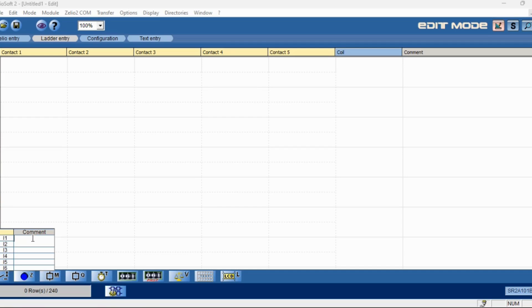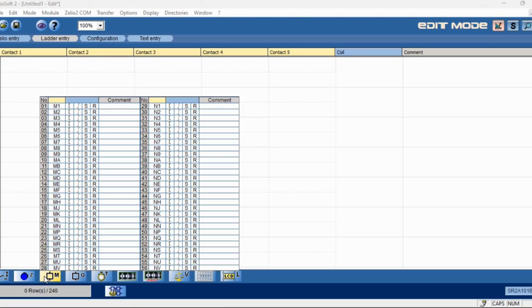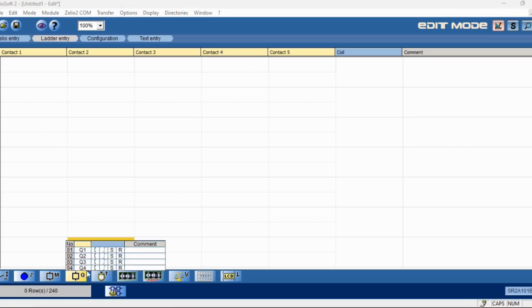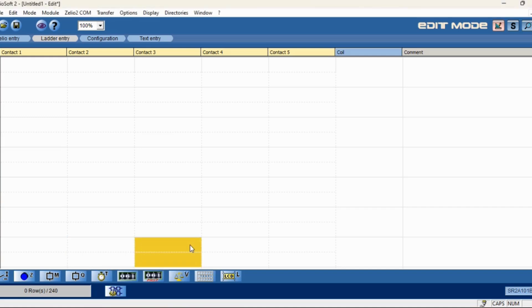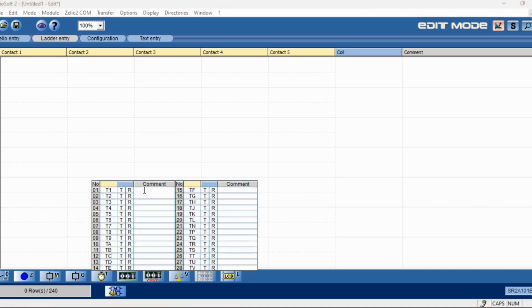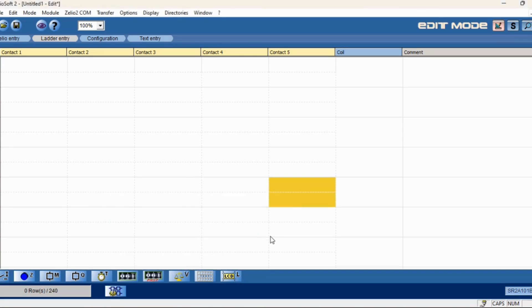First we will assign the digital inputs: start push button as input, and stop push button as input. After that, outputs: output Q1 will be the main contactor, second will be the star contactor, third the delta contactor. Output assigned. After that, timer: on-delay timer, 7 seconds.